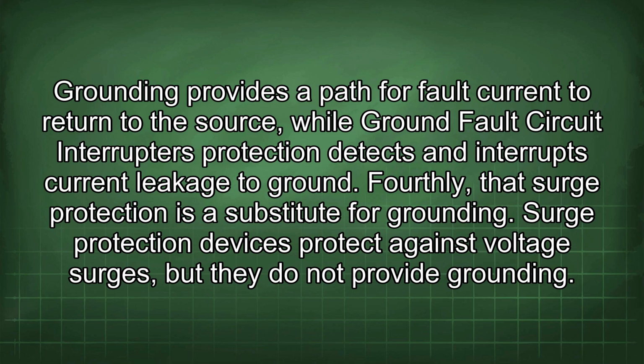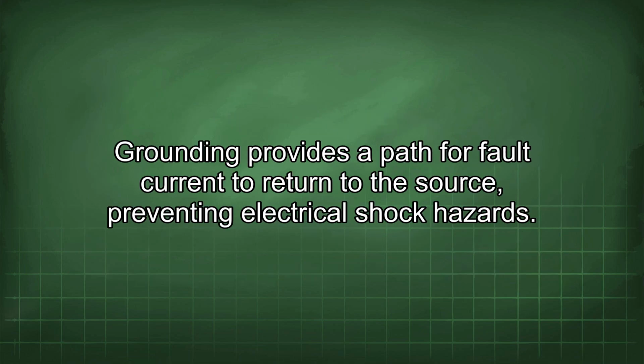Fourthly, that surge protection is a substitute for grounding. Surge protection devices protect against voltage surges, but they do not provide grounding. Grounding provides a path for fault current to return to the source, preventing electrical shock hazards.